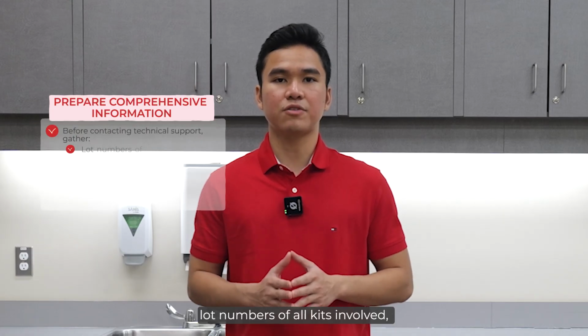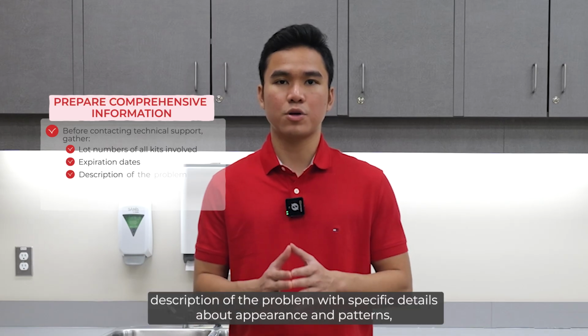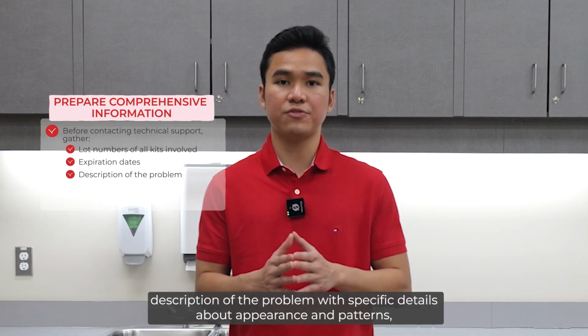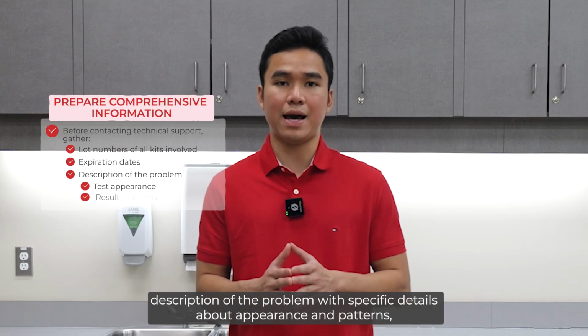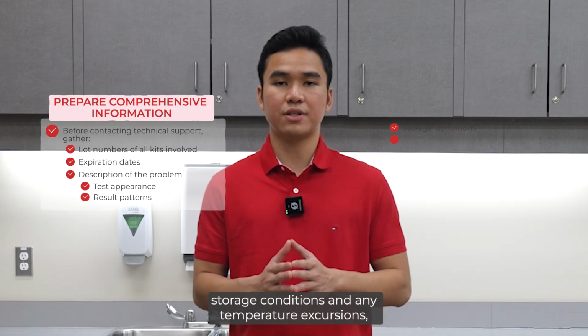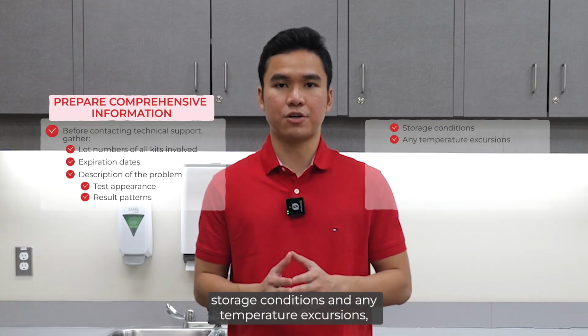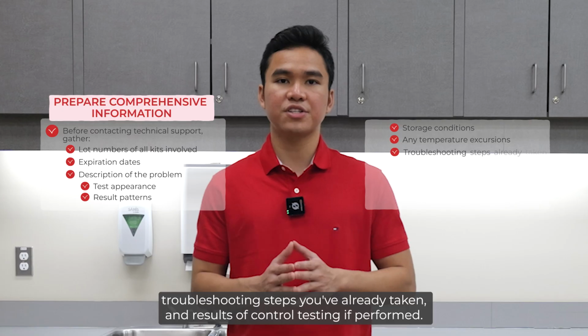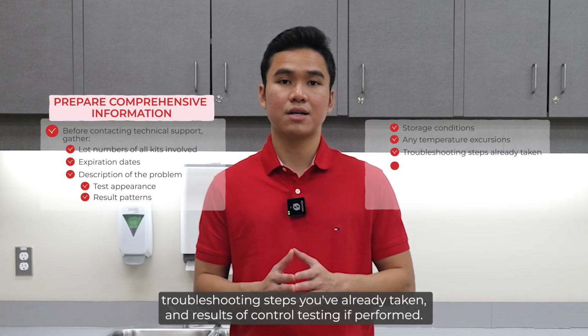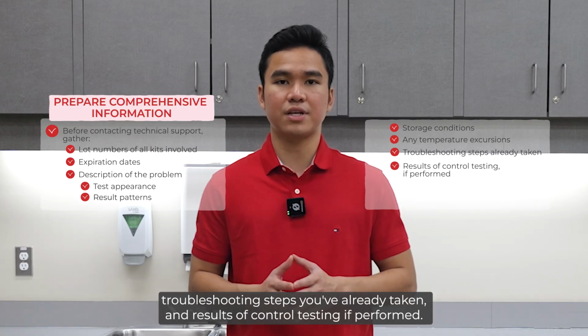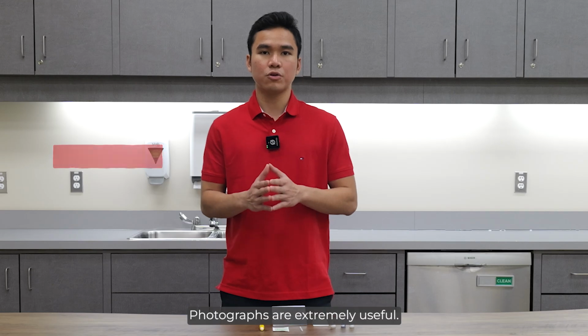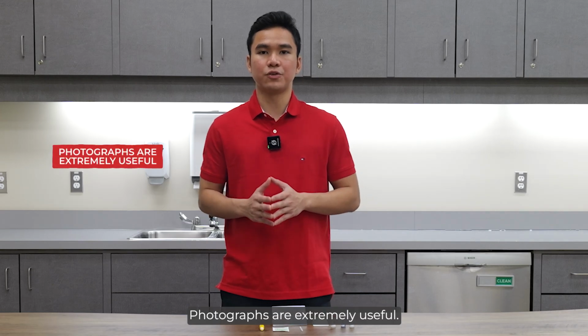When contacting technical support, prepare comprehensive information: lot numbers of all kits involved, expiration dates, description of the problem with specific details about appearance and patterns, storage conditions, and any temperature excursions, troubleshooting steps you've already taken, and results of control testing if performed. Photographs are extremely useful.